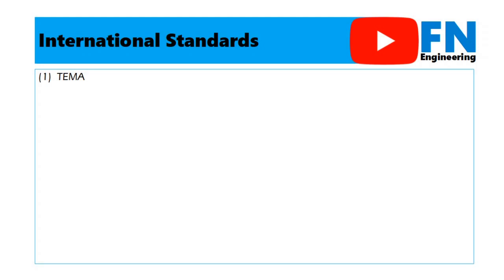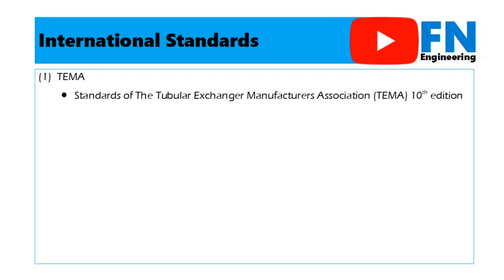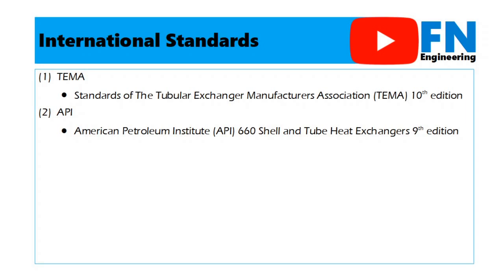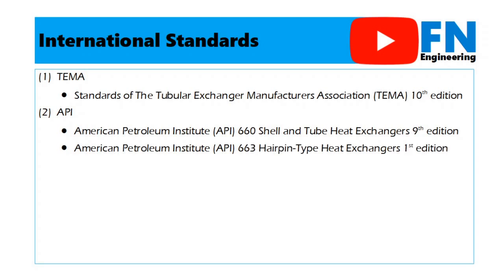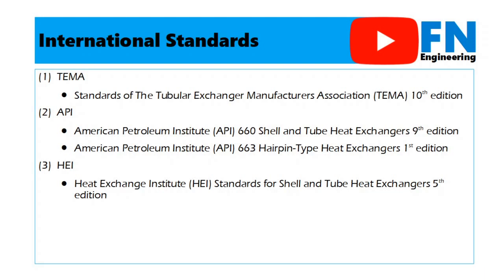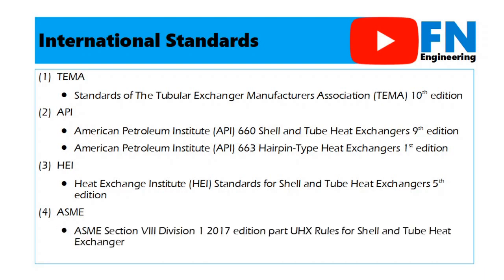First, TEMA, or Standard of Tubular Exchanger Manufacturer Association, 10th edition. Then, API, or American Petroleum Institute 660, Standard for Shell and Tube Heat Exchanger, 9th edition. And API 663 for Hairpin Type Heat Exchanger, 1st edition. Next, HEI, or Heat Exchanger Institute, Standard for Shell and Tube Heat Exchanger, 5th edition. Lastly, ASME, or American Society of Mechanical Engineers, Section 8, Division 1, Part UHX, regarding rules for shell and tube heat exchanger.